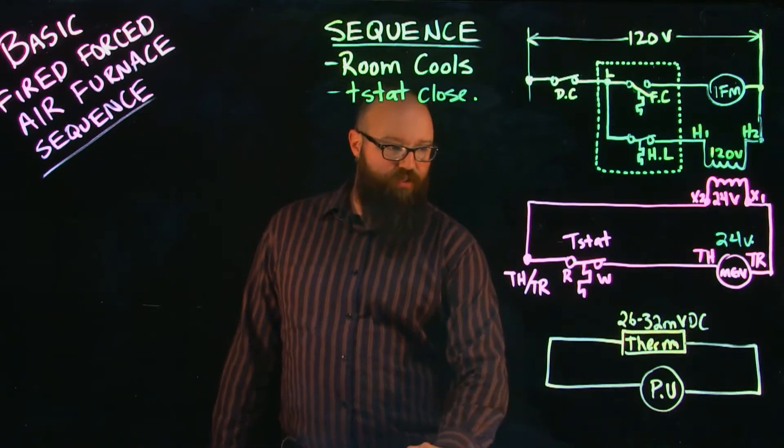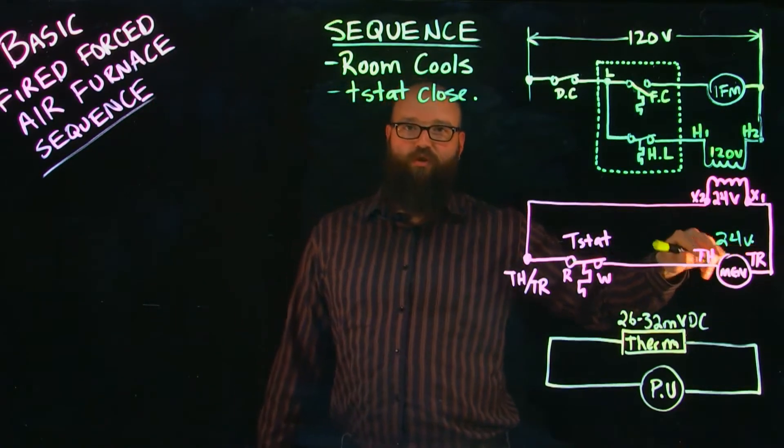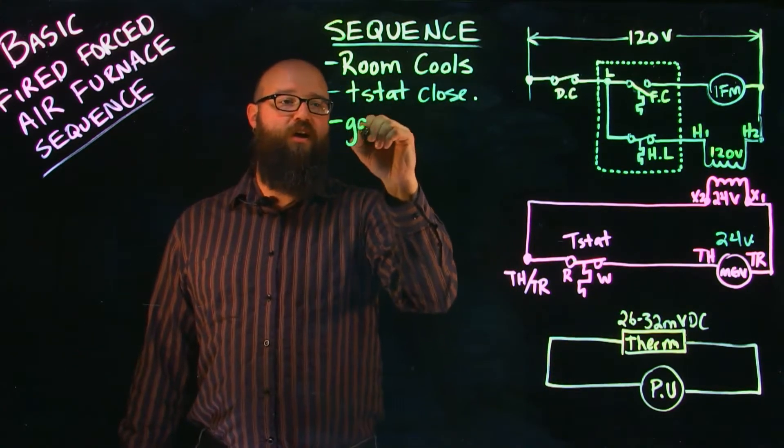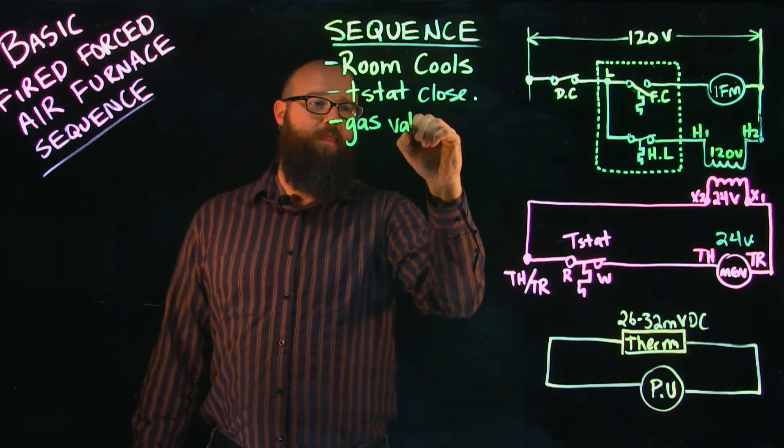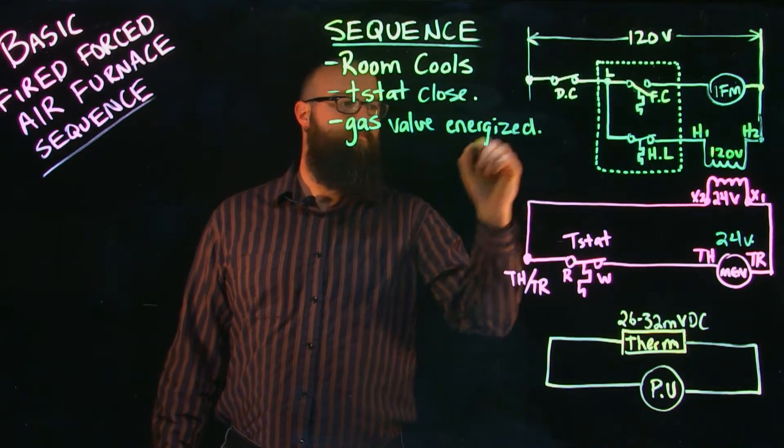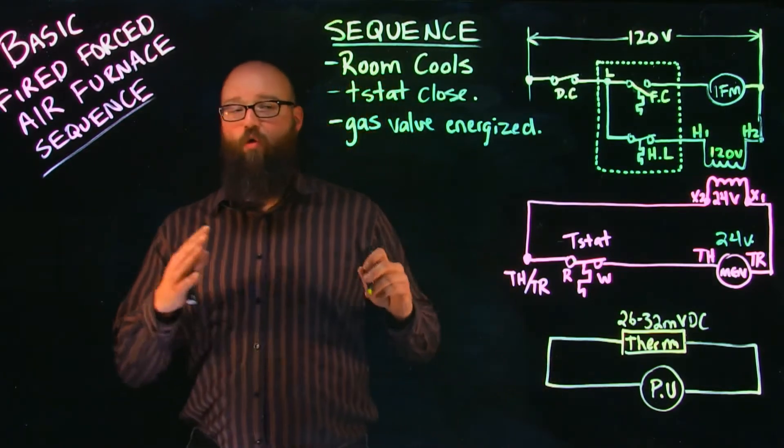So as soon as those thermostat contacts close we are going to see 24 volts across our main gas valve and what that means is our gas valve energizes. Another way of looking at it is our gas valve now opens.